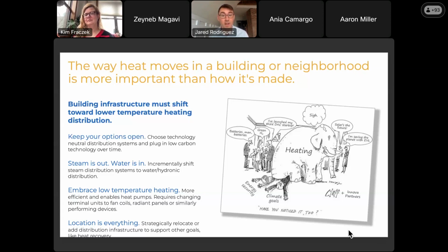It starts with enabling steps, moving to lower temperature distribution, choosing technology neutral distribution systems, low temperature hydronics. Hydronics are technology neutral in that any source of heat can plug in over time, and any type of thermal energy storage could plug in over time. Steam is out, water is in.